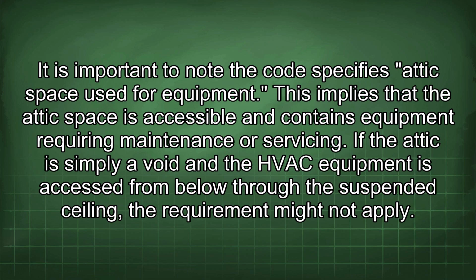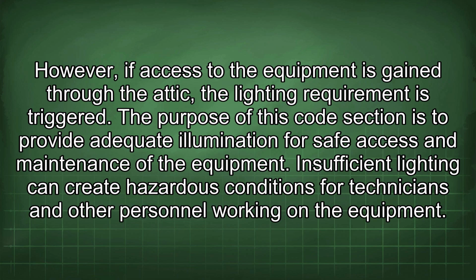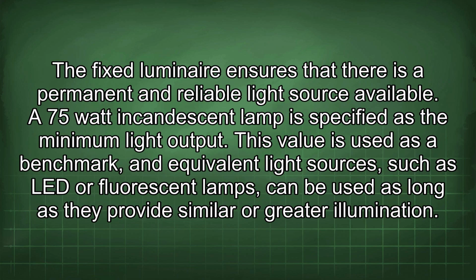If the attic is simply a void and the HVAC equipment is accessed from below through the suspended ceiling, the requirement might not apply. However, if access to the equipment is gained through the attic, the lighting requirement is triggered. The purpose of this code section is to provide adequate illumination for safe access and maintenance of the equipment. Insufficient lighting can create hazardous conditions for technicians and other personnel working on the equipment. The fixed luminaire ensures that there is a permanent and reliable light source available.